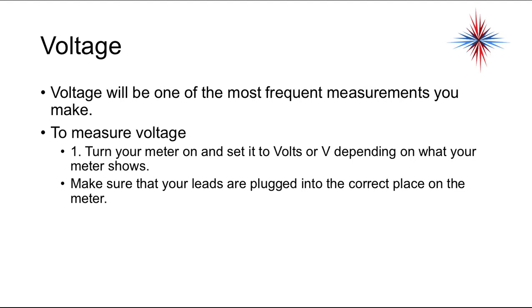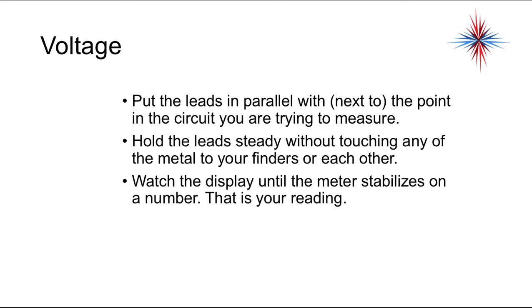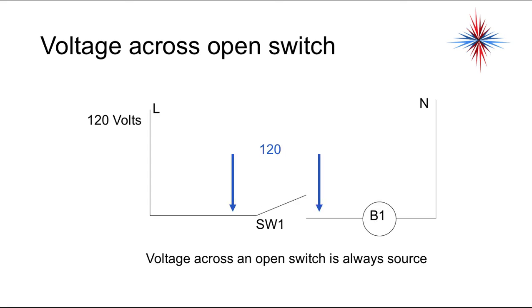To measure voltage, turn your meter on, set it to volts or V, make sure you have AC or DC set properly, okay, and make sure your leads are plugged into the correct place on the meter. Put the leads in parallel or next to the point in the circuit you're trying to measure. Your meter with voltage will always be in parallel with the circuit you're trying to measure. Hold the lead steady without touching any of the metal to your fingers or each other. Watch the display until the meter stabilizes on a number. That is your voltage reading.